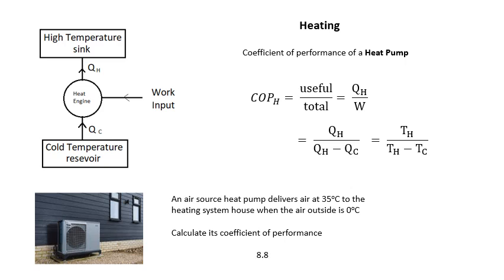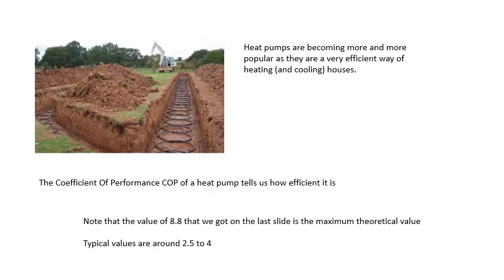The answer is 8.8 — this is the maximum theoretical coefficient of performance. You're not going to get 8.8 in practice. Heat pumps are becoming more and more popular because they're a very efficient way of keeping your house warm. The coefficient of performance of a heat pump tells us basically how efficient it is. 8.8 is a maximum theoretical value; typical values are from about 2.5 to 4. They are actually more efficient in the summer than in the winter — 2.5 would be a winter value, 4 would be a summer value.